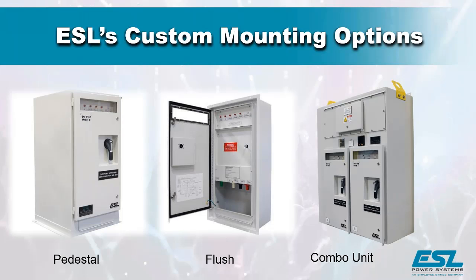Over on the right, the Big Daddy combo unit that I mentioned earlier. It's really 2 company switches inside of a giant cabinet. What you see up on the top portion could be a main circuit breaker if the customer desires, or we just land on a PDB. The contractor comes in and lands on a power distribution block, and then we factory wire from that to the company switch sections here at the factory. This combo unit also has the 3-phase light setup I described earlier, and lifting eyes at the top as well, which are removable.